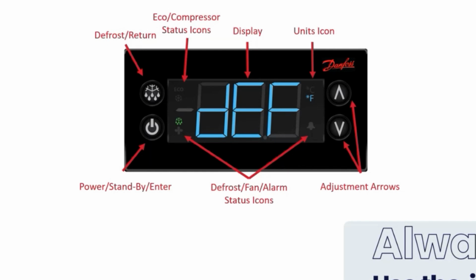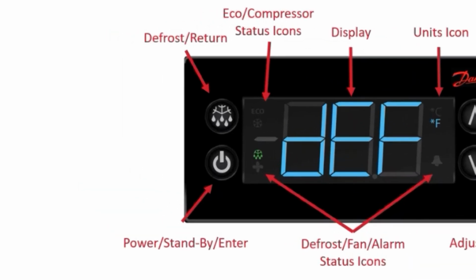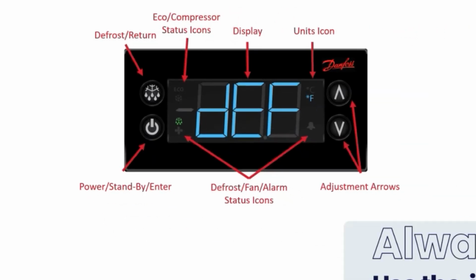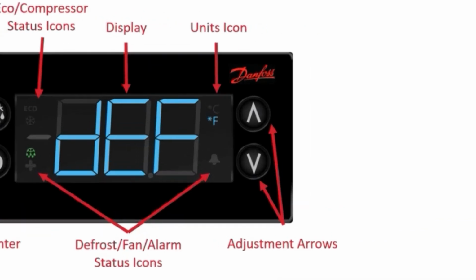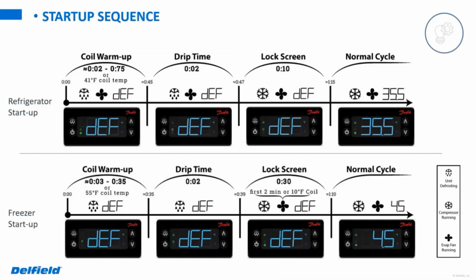because as we'll mention here, as far as defrost goes, the defrost can be a little bit tricky. If you just look at the display and see DEF, you may actually see a time that the unit's actually cooling and showing that, and we'll explain that in the next few slides. And you also have your buttons around the outside as well. We have your defrost button and power buttons, but on these ones we got them separated. The adjustment arrows are on the right hand side of the display as you look at it.